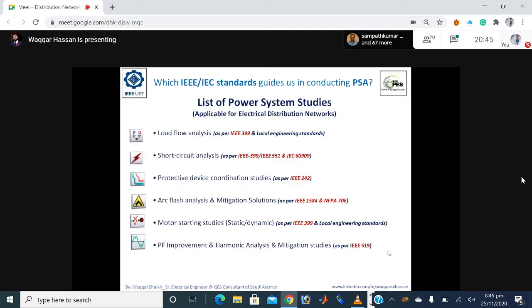Similarly, for earthing studies related to step voltage and touch voltage potentials, IEEE standard 80 is very important to understand. For protection coordination studies, which help determine relay settings, IEEE standard 242 is very important. For harmonic analysis, IEEE 519 gives us the limits for total harmonic distortion with respect to currents and voltages.